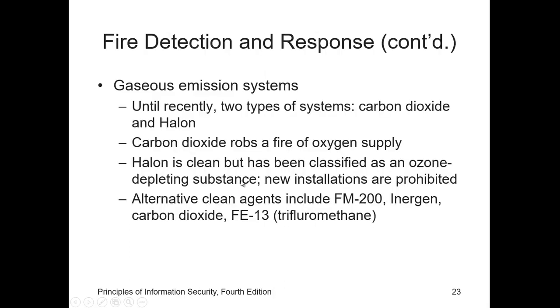The gaseous emission systems use chemical gas systems which suppress the fire. Until recently, there were only two major types of gaseous systems: carbon dioxide and halon. Carbon dioxide deprives a fire of its oxygen supply. Halon is a clean agent, which means it does not leave any residue when dry, nor does it interfere with the operation of electrical or electronic equipment. Unfortunately, the EPA has classified halon as an ozone-depleting substance and therefore new installations are prohibited.